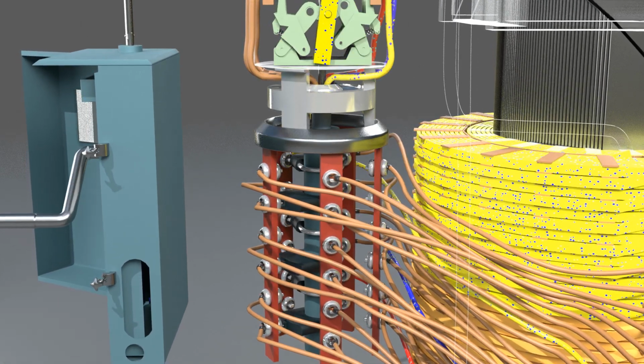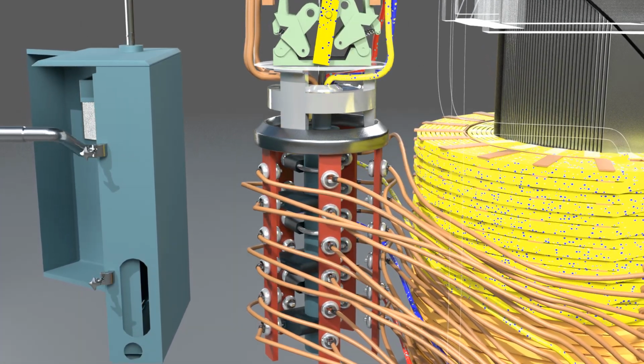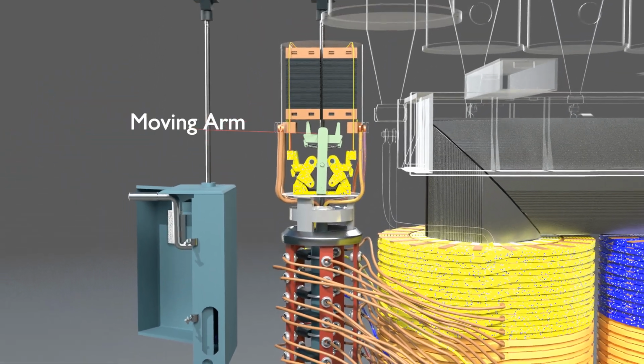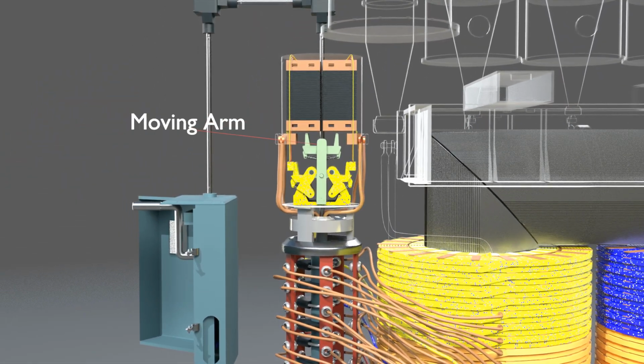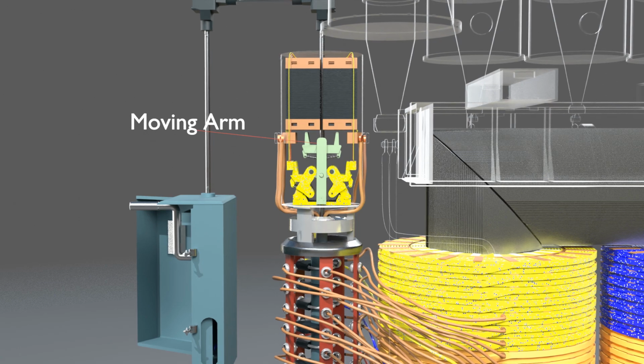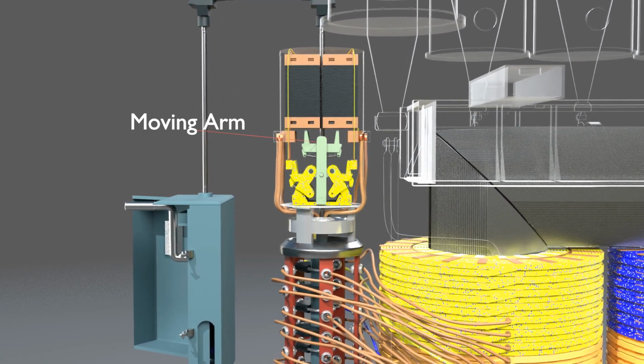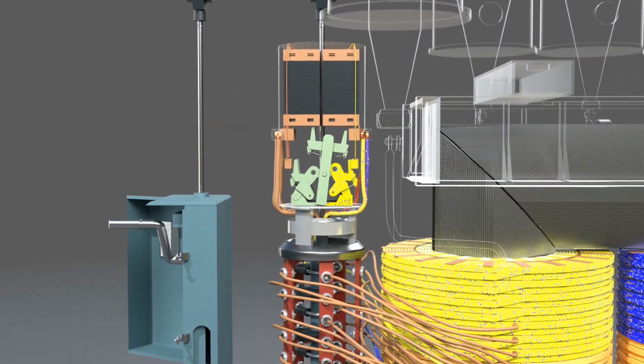The OLTC consists of a moving arm, which swings left and right like a pendulum to make contact with different tap positions. This movement allows the transformer to adjust the voltage under load without interruption.